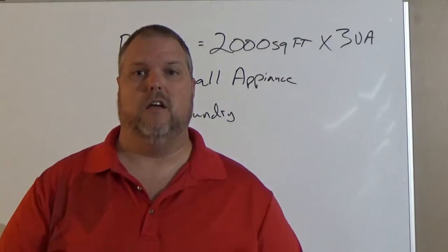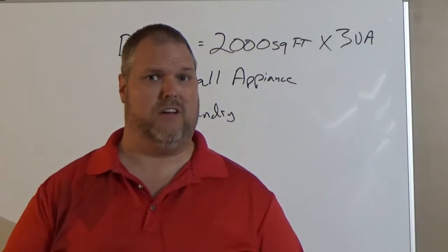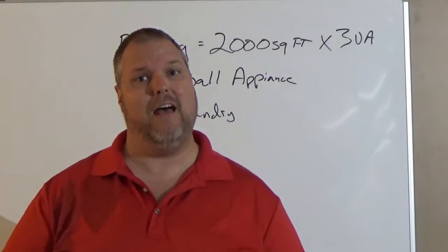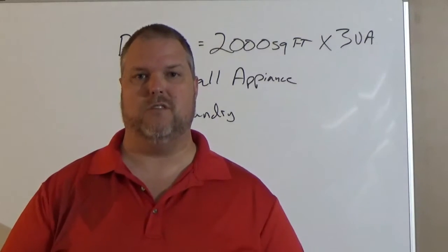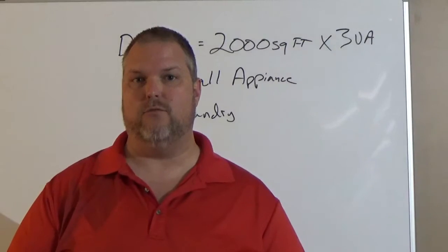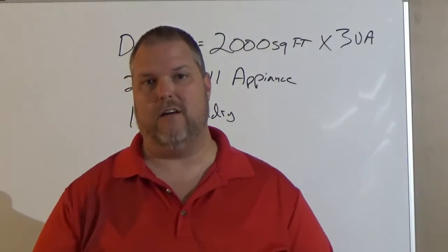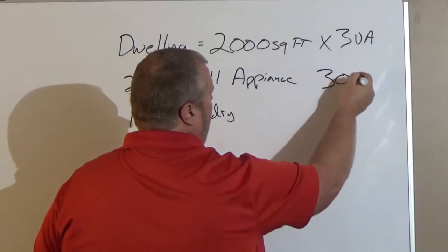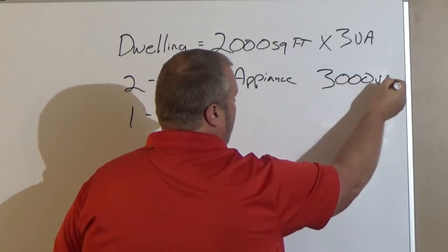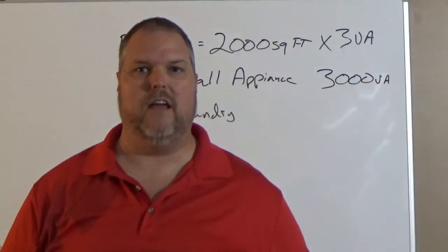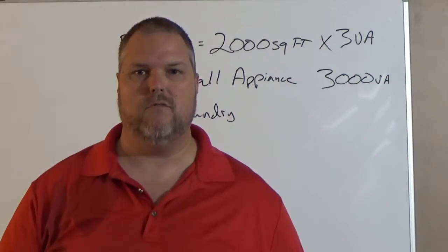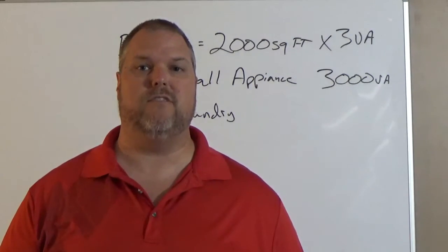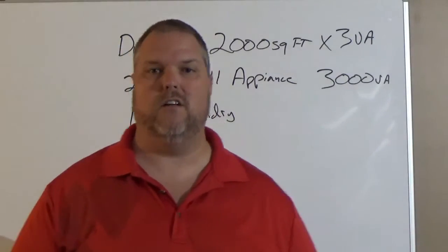If you have a minimum of 2, which you have to have 2, you can have 3, you can have 4, you can have 5, you can have as many as you want. Just remember that every 1 after that, you've got to add 1,500 VA. So our small appliance circuit, if we're only doing 2 small appliance circuits, we have to multiply it by 2, which gives us 3,000 VA. Same thing with our laundry circuit. Our laundry circuit is 1,500 VA. So we're going to add 1,500 in.